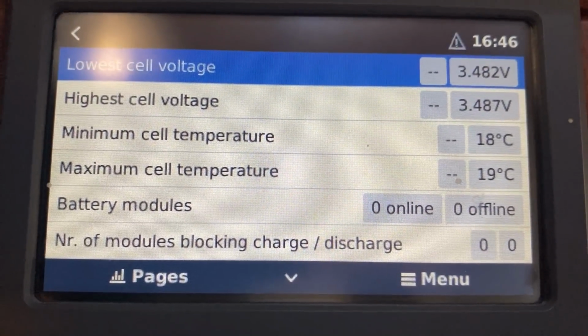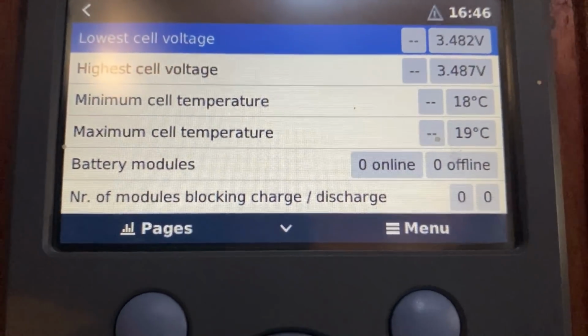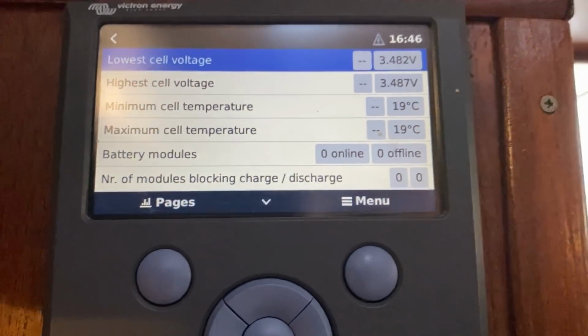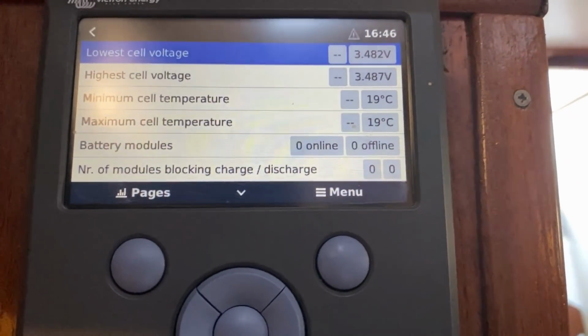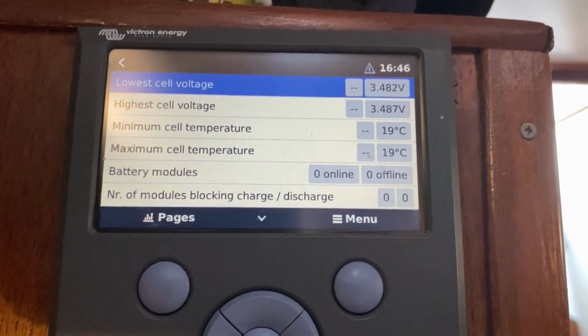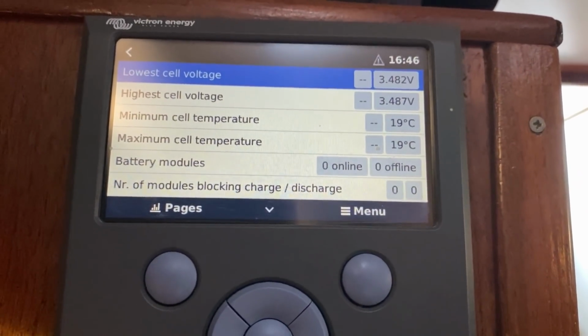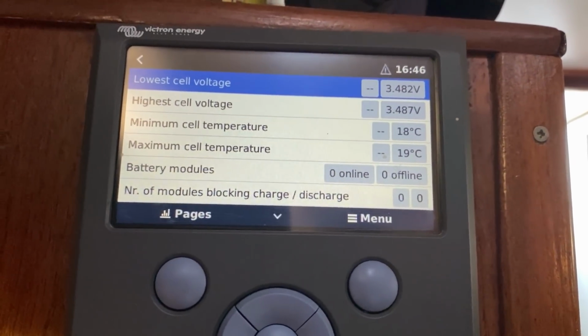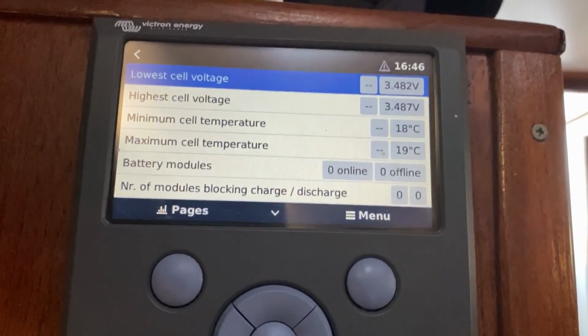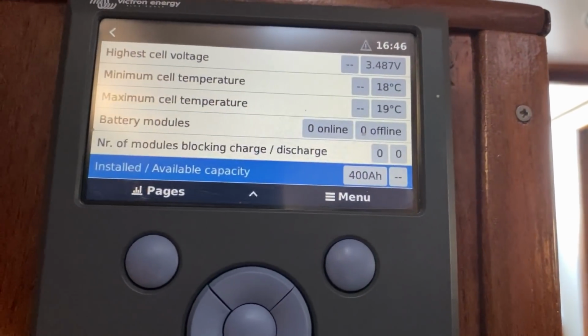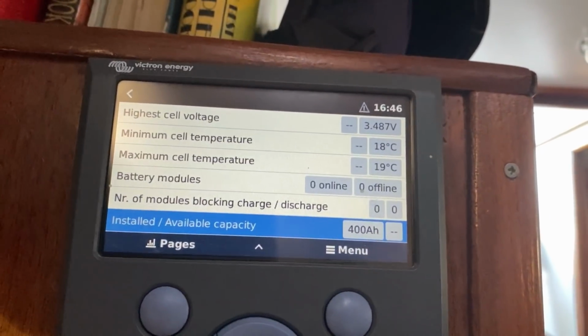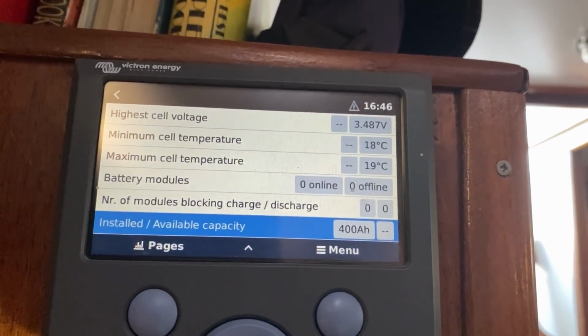That's one of the most critical things on this CCGX to think about. The minimum and maximum cell temperature is probably important too - you don't want a huge difference between those. And installed available capacity is still 400 amp hours. So those are all important things to look at.